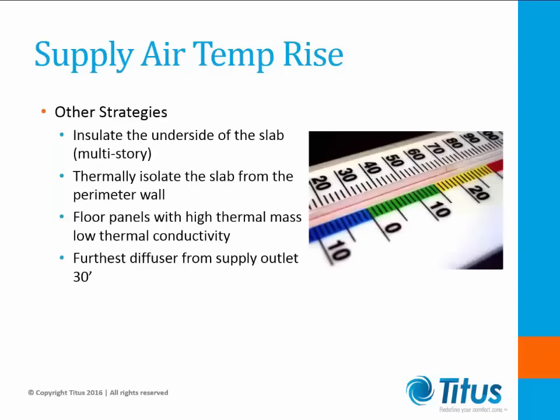There are other strategies that can be employed to reduce supply air temperature rise besides partitions. These include insulating the underside of each floor slab in a multi-story building, isolating the floor slabs from the perimeter walls, selecting floor panels with high thermal mass and low thermal conductivity, and using more ductwork to get within 30 feet of the furthest diffuser.